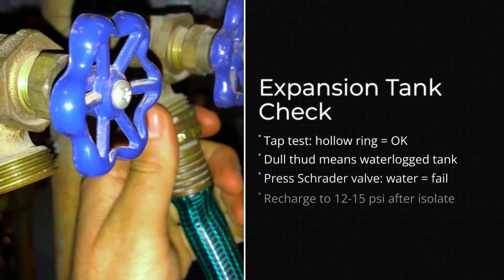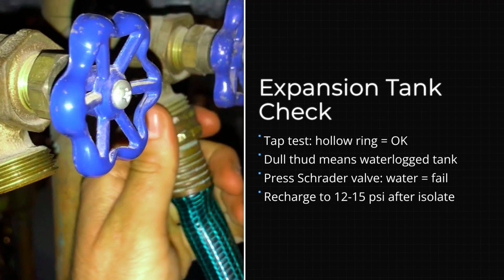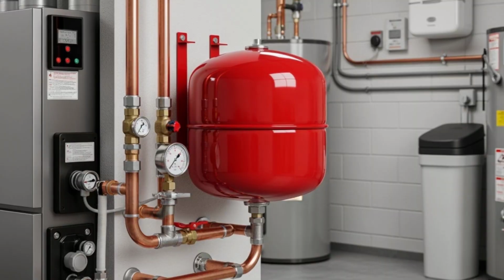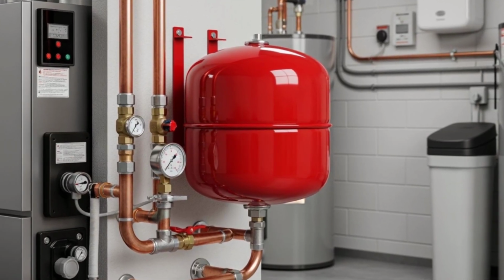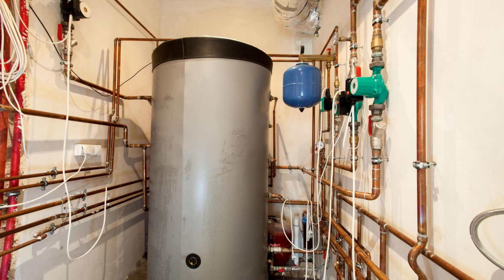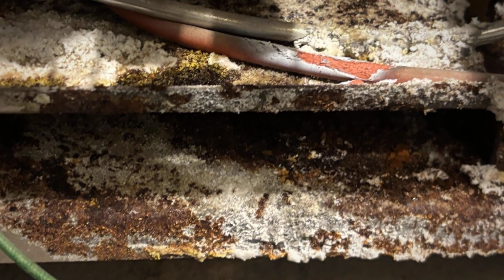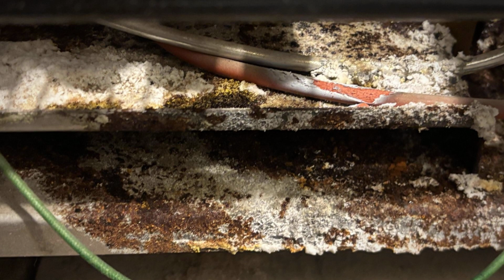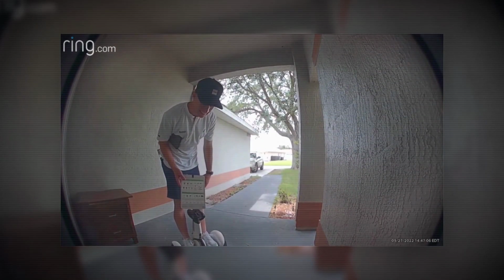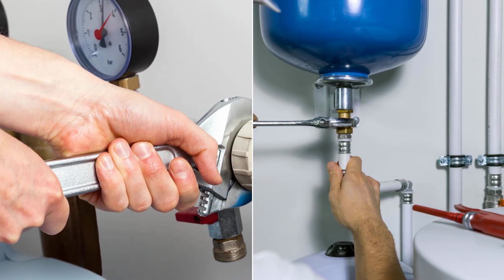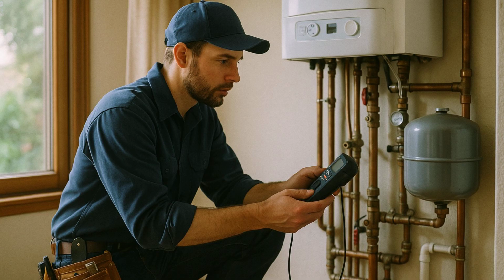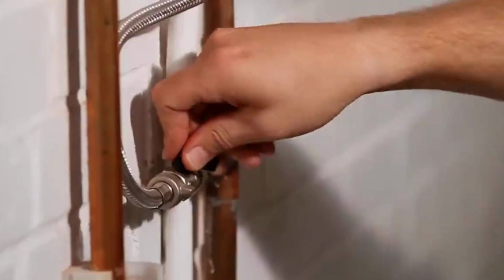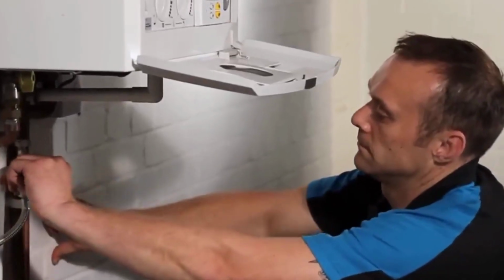Shut down the boiler, isolate the tank, bleed off pressure, and add air up to spec. A properly charged tank relieves daily expansion, prevents relief valve blow-offs, and can add 8 to 15 years to your boiler's life. Ignore it and you invite short cycling, corrosion, and catastrophic exchanger cracks, the exact kind of failure that lines the pockets of HVAC salesmen. This is the line between safe, do-it-yourself, and danger. If water comes out the air valve, call a pro. Otherwise, do not let anyone sell you a new boiler just because your tank lost its air.